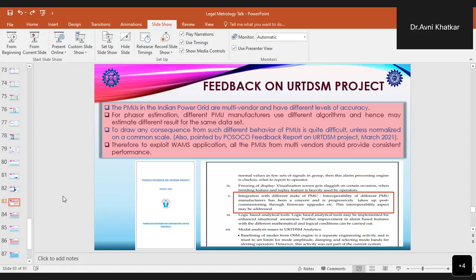For phasor estimation, the PMUs from different manufacturers are using different algorithms. So the phasor estimation method they are using is different, and so we are getting different results. So it is very difficult to draw any conclusions from these different behaviors of the PMUs, unless they are normalized on a common scale. This was also pointed out by the POSOCO feedback report. Therefore, to exploit them in WAMS applications, all these PMUs from different vendors should provide consistent performance.